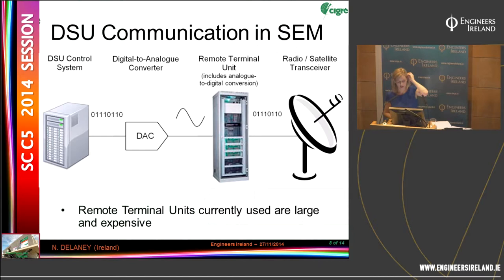Another aspect of the paper discusses facilitating communication with demand-side units. Although demand-side units are treated like a type of generator in the market, they're generally quite small-scale, cost-sensitive businesses. At the moment, for communicating between a generator and the National Control Centre, the only means up until now has been a remote terminal unit. And remote terminal units are quite large, about 1 metre cubed, and relatively expensive. So the RTU and cabling and communications will cost about €31,000.